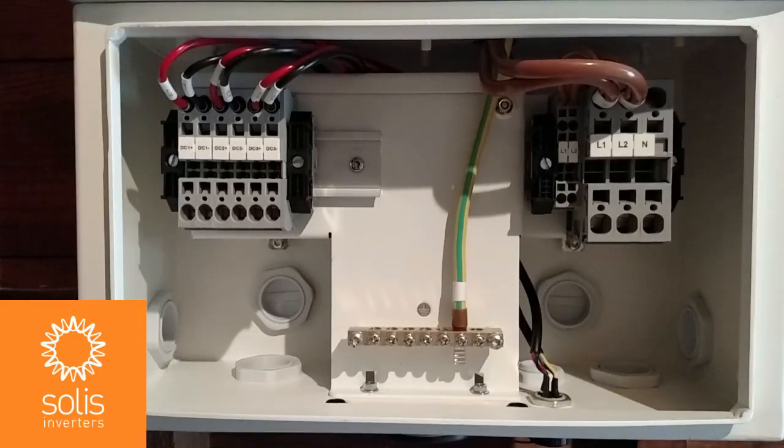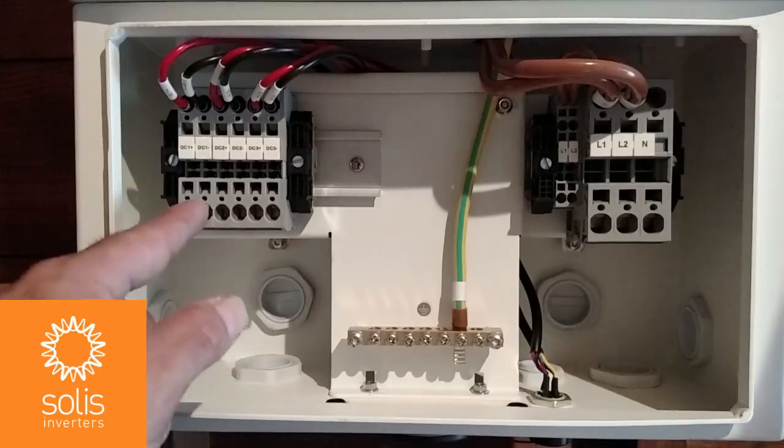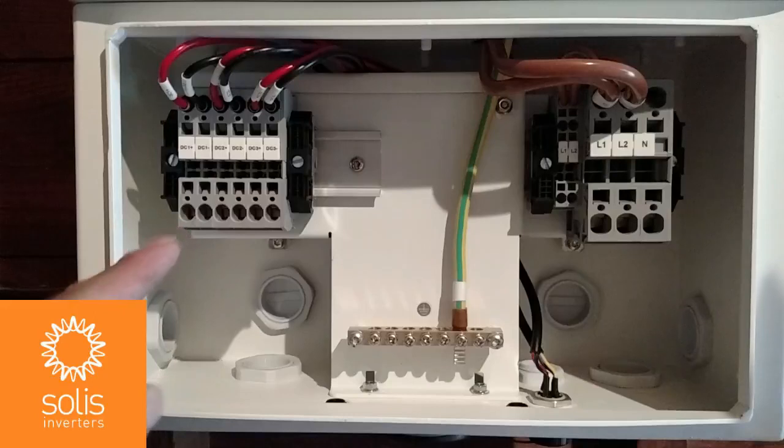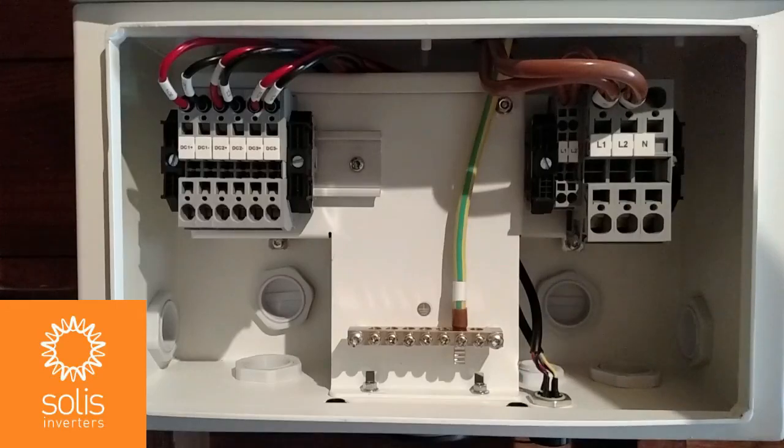All knockouts come with gasketed knockout plugs. These plugs and weather-tight conduit fittings will ensure your completed inverter installation retains its NEMA 4X rating. Inside, you can see the multiple MPPT inputs for the DC PV conductors. This particular inverter has three independent MPPTs. Depending on the model, you may see two, three, or four MPPTs on the Solis North American inverters 2.5K through 10K.